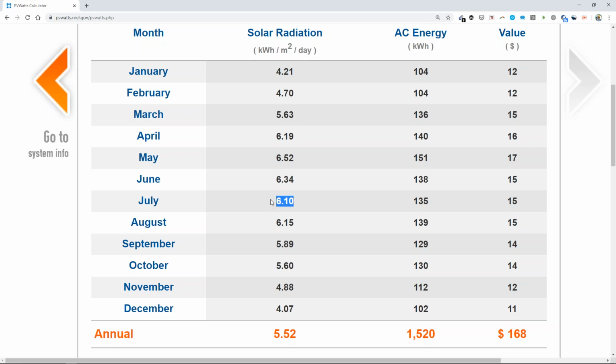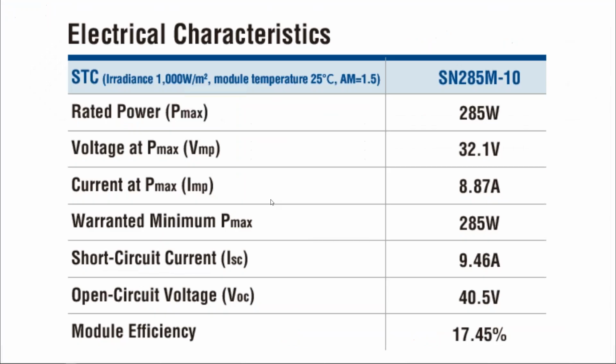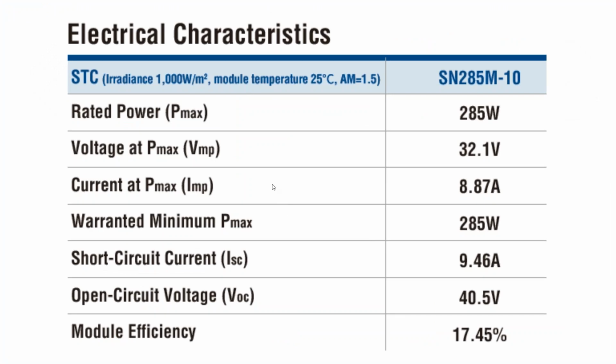The sun hour concept was really popular back before computers, when they did solar design, to have these kinds of fudge factors to say, well, how many sun hours do you get in your area? And then you could take the efficiency numbers from the spec sheet and develop a performance estimate off that. It's kind of an antiquated design practice, but still useful to know about. It all revolves around this 1,000-watt per meter squared concept.